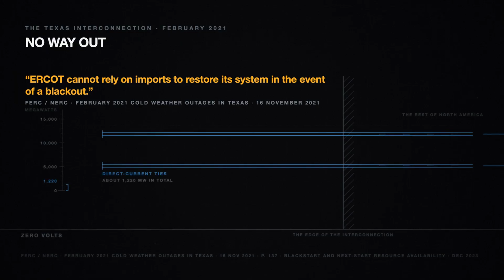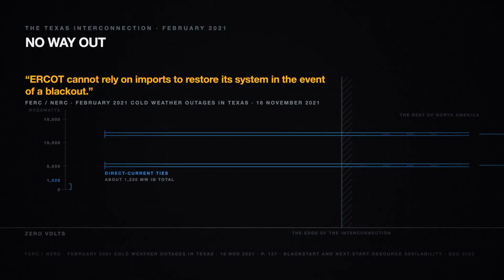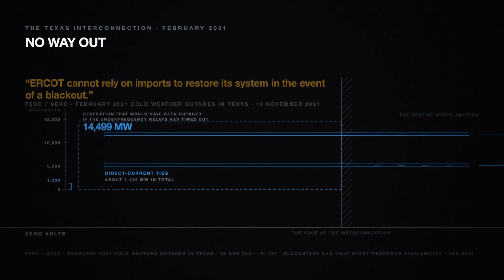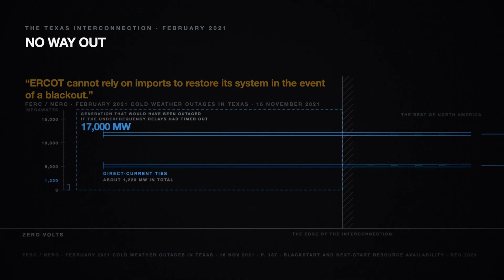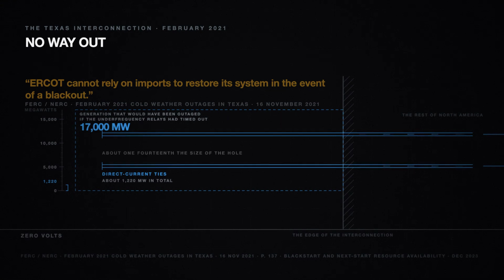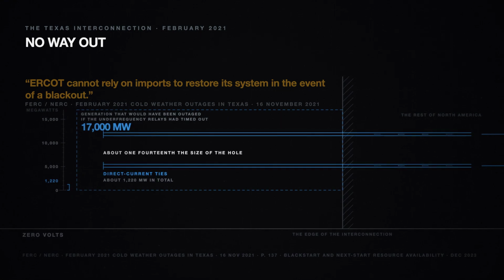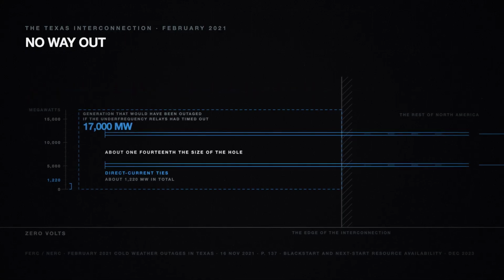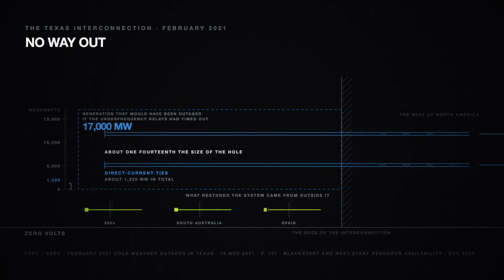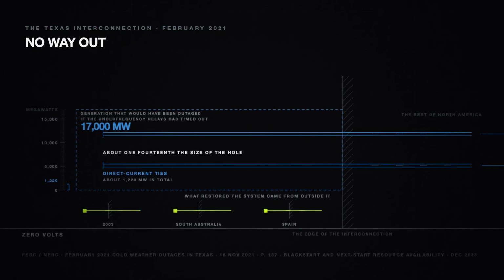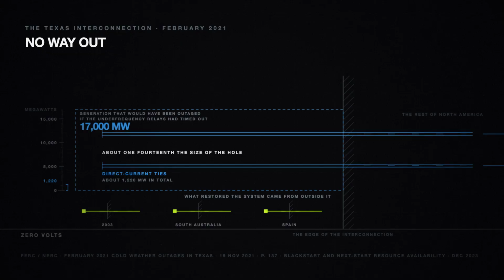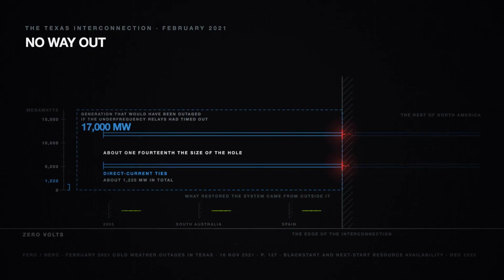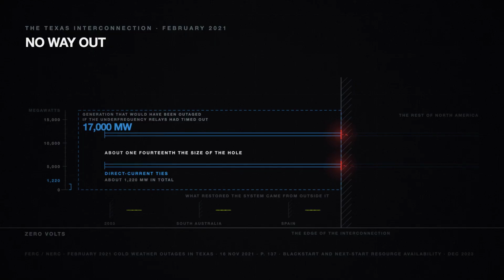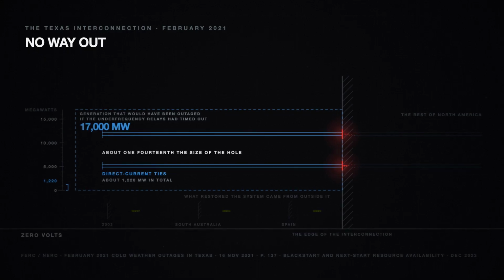Its links to the rest of North America are direct current ties, totaling about 1,220 megawatts. Set that against the 17,000 megawatts that would have disconnected if those relay timers had run out. The way back in is about 1/14 the size of the hole. In 3 of the cases in this film, 2003, South Australia, Spain, what restored the system came from outside it. For Texas, that door is not there, which puts more weight on the written plan than anywhere else, and raises the obvious question: how fast is it supposed to work?